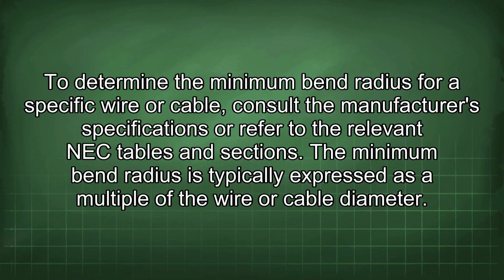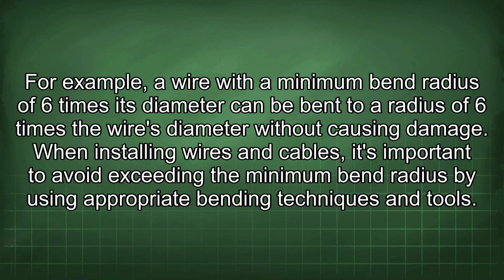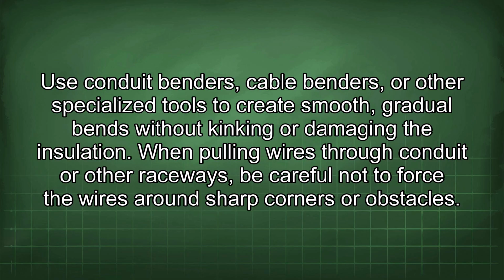To determine the minimum bend radius for a specific wire or cable, consult the manufacturer's specifications or refer to the relevant NEC tables and sections. The minimum bend radius is typically expressed as a multiple of the wire or cable diameter. For example, a wire with a minimum bend radius of 6 times its diameter can be bent to a radius of 6 times the wire's diameter without causing damage. When installing wires and cables, it's important to avoid exceeding the minimum bend radius by using appropriate bending techniques and tools. Use conduit benders, cable benders, or other specialized tools to create smooth, gradual bends without kinking or damaging the insulation.